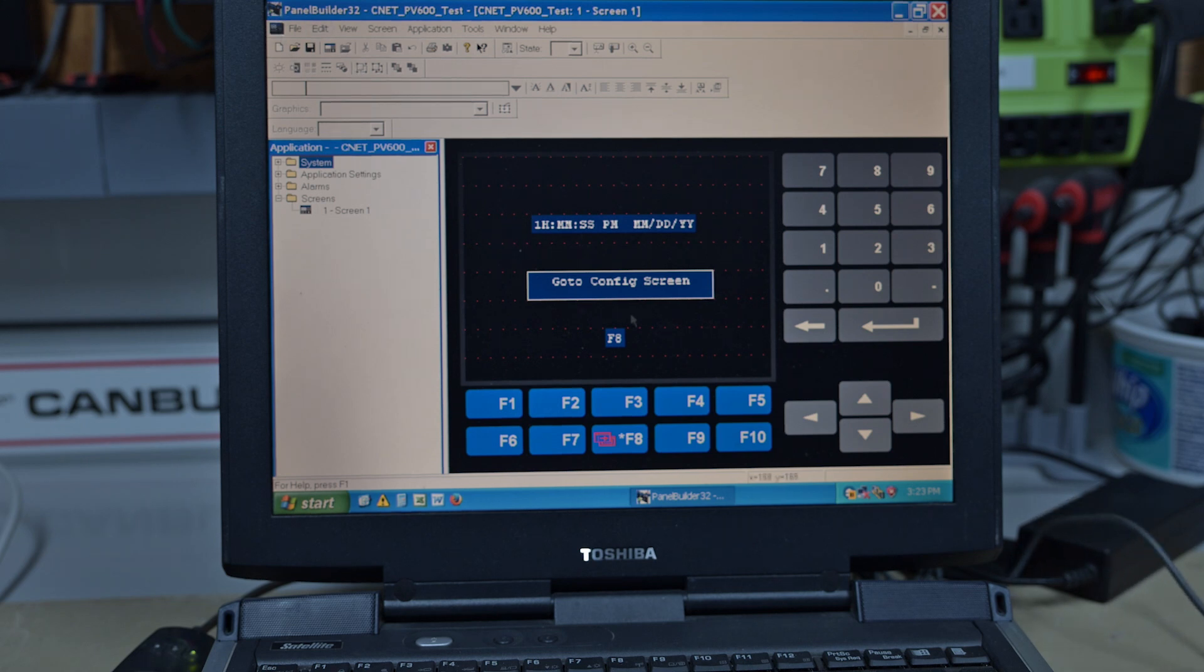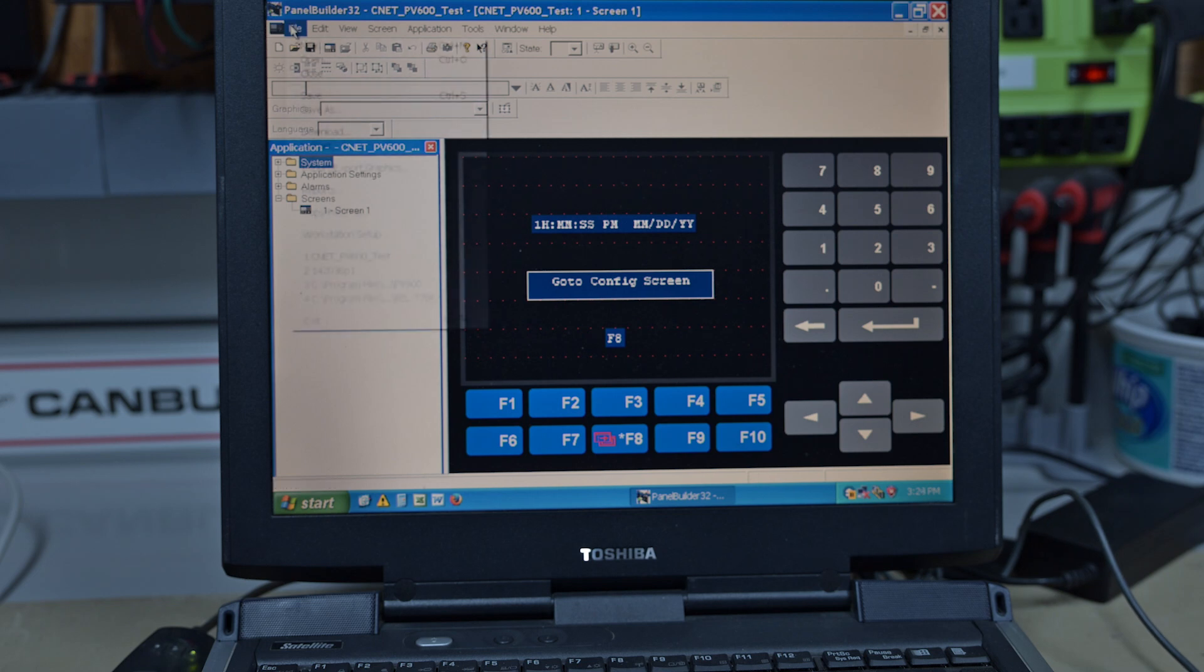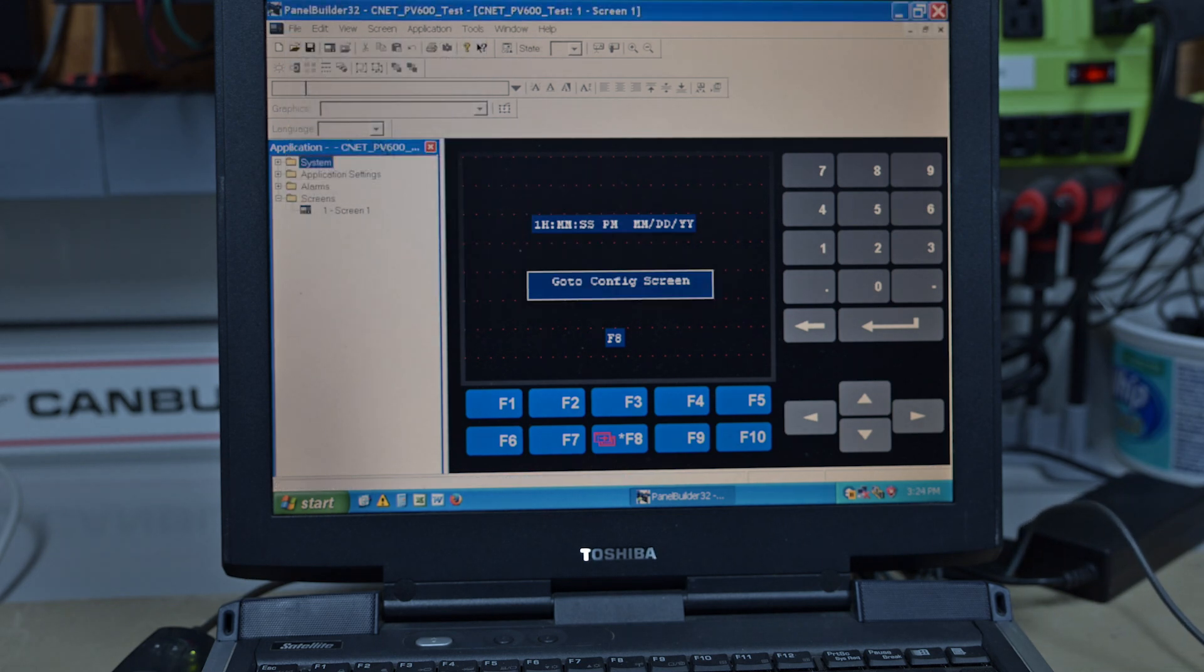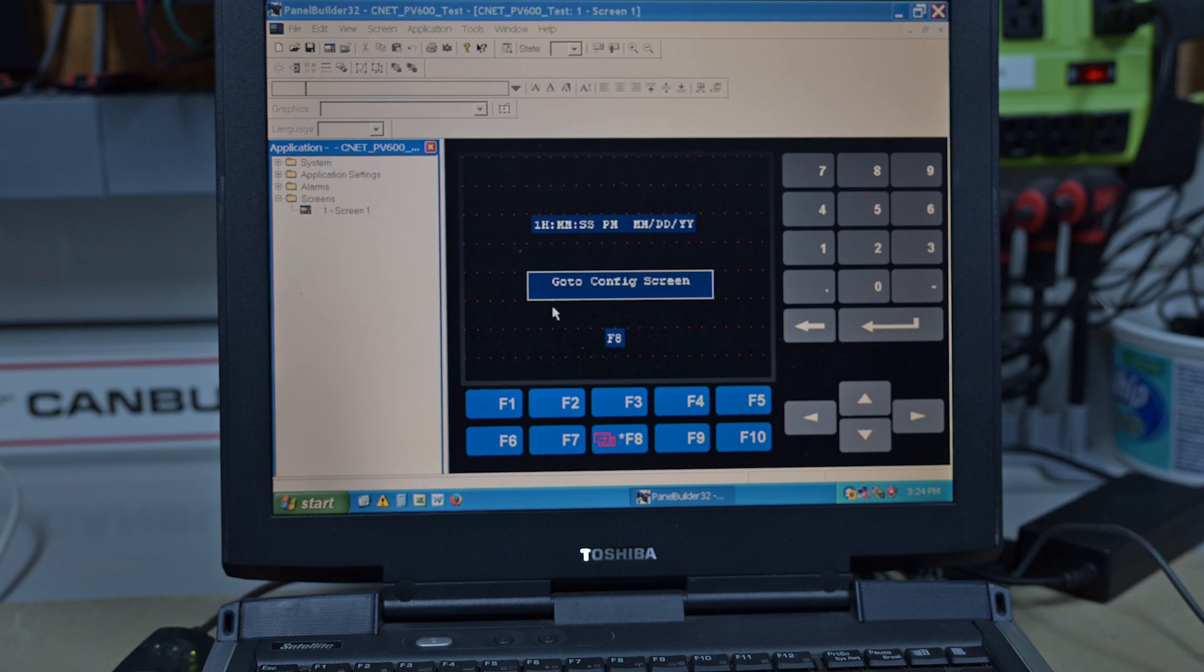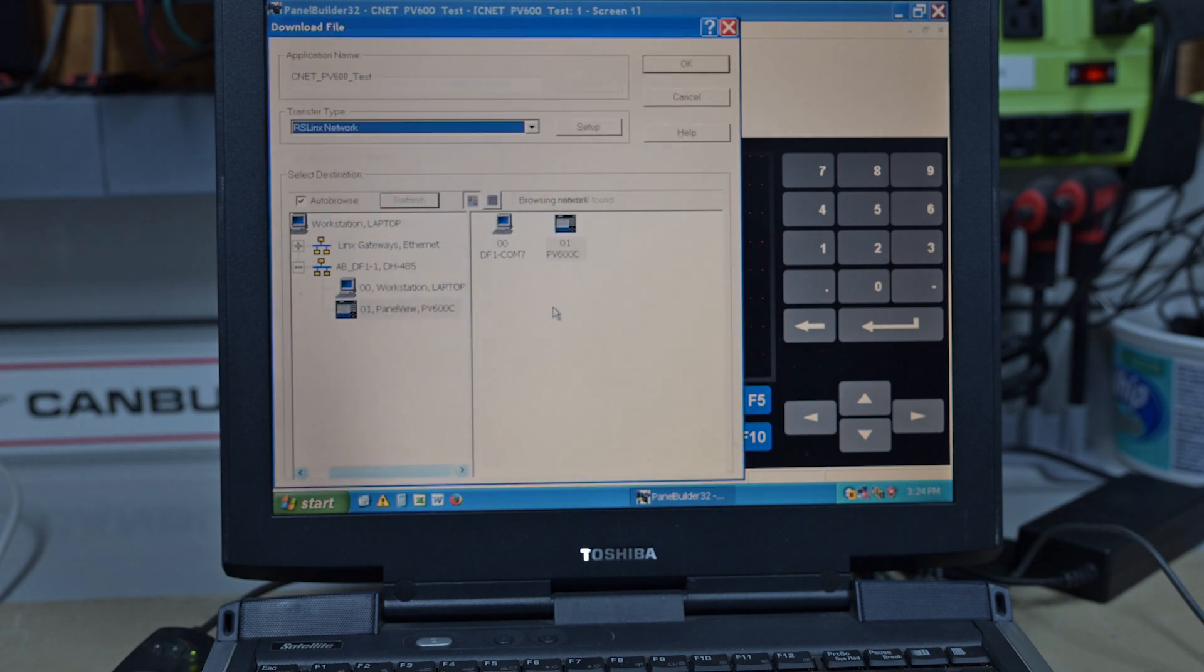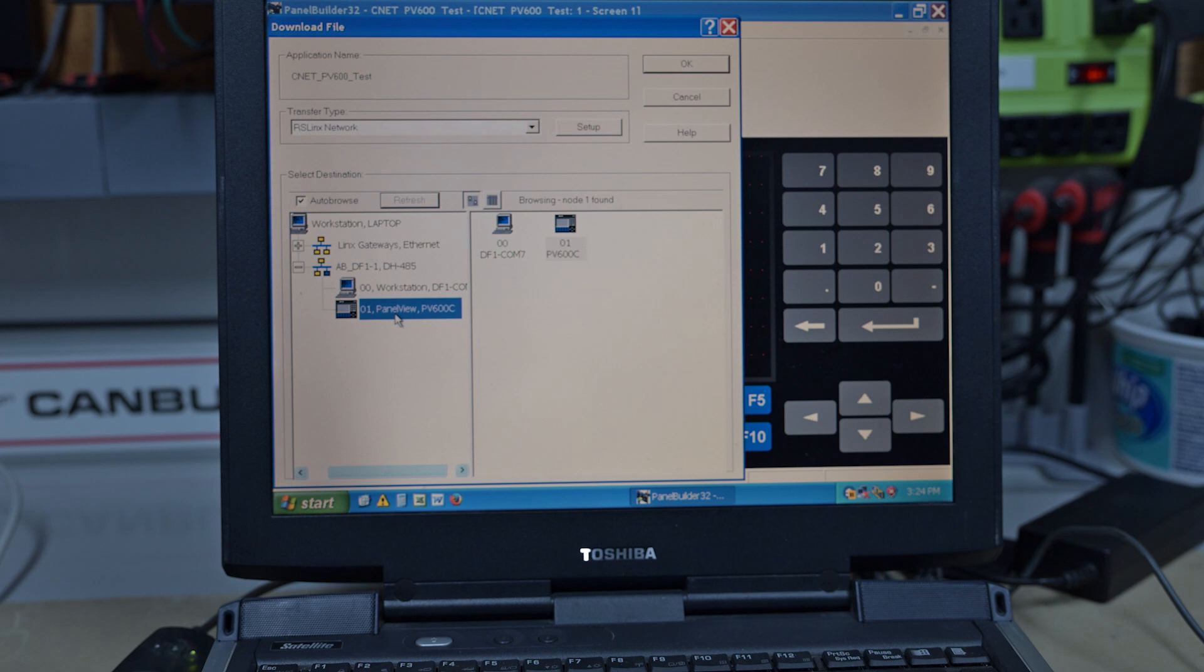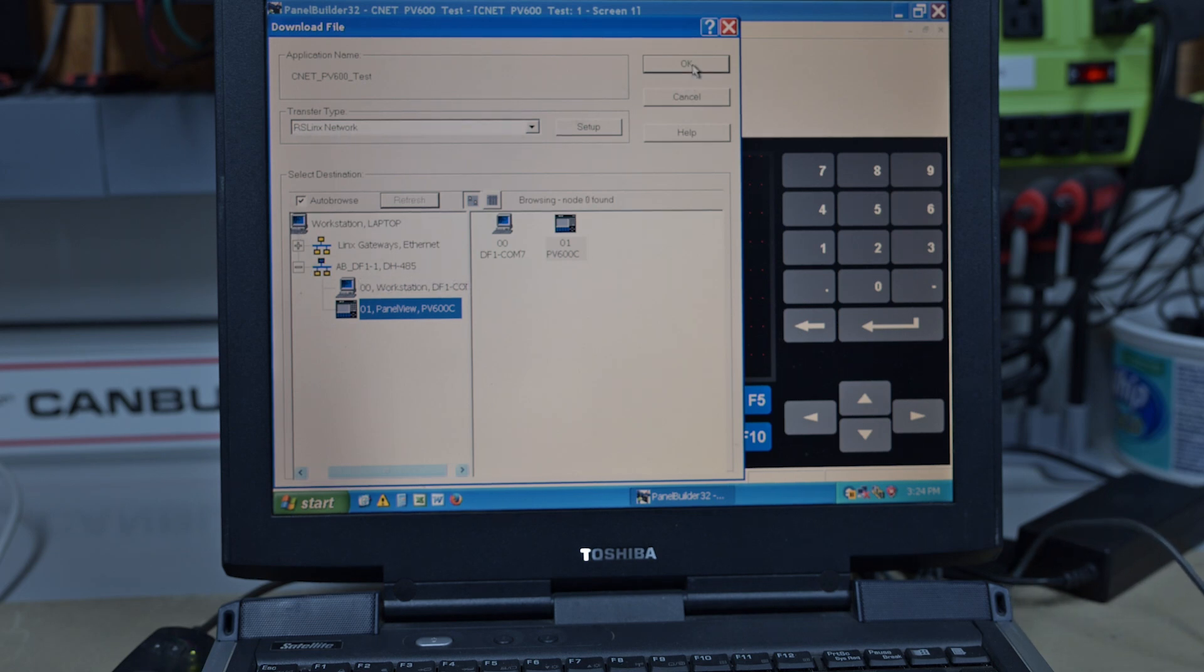So what we want to do is download this to our Panel View. So we go File, Download. It goes through, it checks everything, make sure there's no warnings, buttons overlapping each other, text overlapping, whatever. And we pick our Panel View. You have to highlight it and we're using RSLinx Network, which we already have set up because there it is. And hit OK.